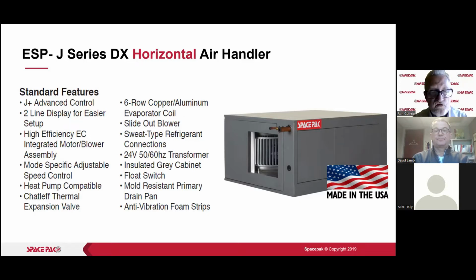It is mode specific adjustable, so we can have different speeds for cooling, for heating, cooling stage 1 or 2, heating stage 1 or 2 fan, even during defrost, or if we're going to do humidification, we can have that run at a separate speed. Okay, so it's very versatile as far as being able to control the speed to what we feel is going to be the best speed for that particular application of the air handler.